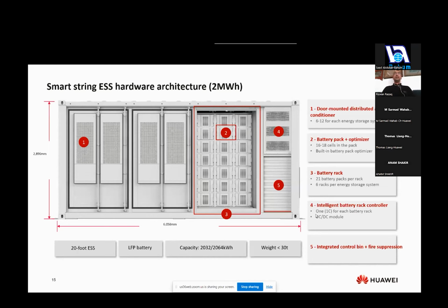So for the utility scale application, a slightly larger capacity, we are working with a 20-foot container, very similar type of solution, but these are now broken down into several different sections. So once again, the distributed air conditioning systems are mounted on the doors of the units themselves. Section number 2 is your battery pack and optimizer. So there's 16 to 18 cells in each pack, with a built-in battery pack optimizer. And section number 3 is your battery rack. So overall, there are 21 battery packs per rack and 6 racks per energy storage system. So this will give you the total capacity of around 2.064 megawatt hour overall, available in one container.